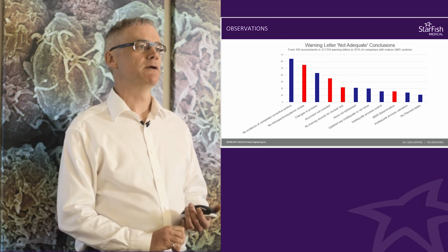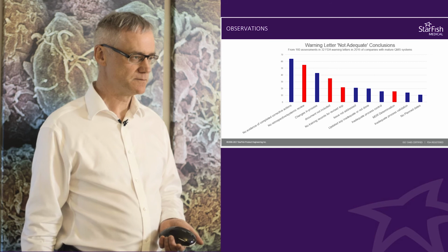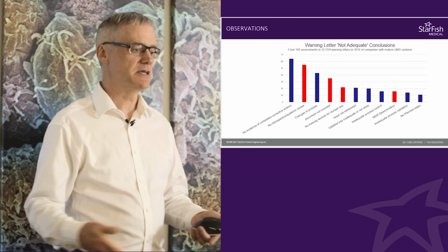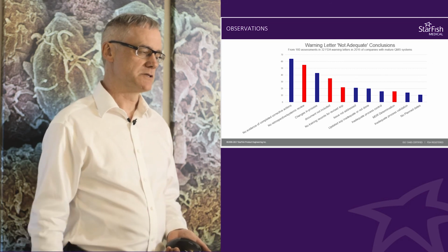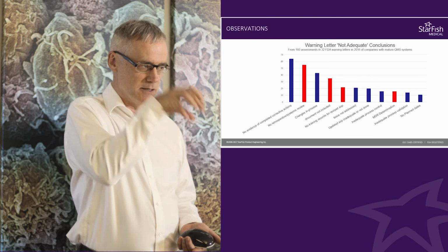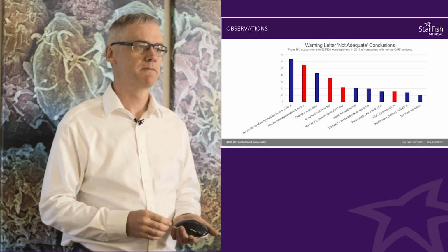However, the number two reason, which was over 50% of the findings, was no retrospective or systemic review. I didn't split them apart, but that one is actually a pretty easy one. Maybe it's not easy to do, but I believe companies just didn't realize they needed to do that. The warning letter or the finding is not just a finding of that one thing, where you correct the one thing and you're good. It's actually representative of other things that might be similar.